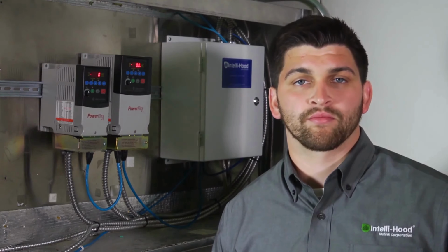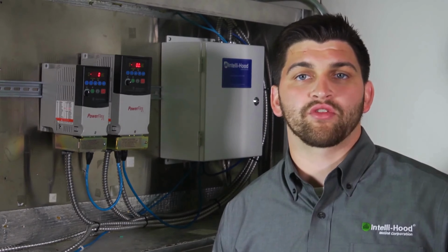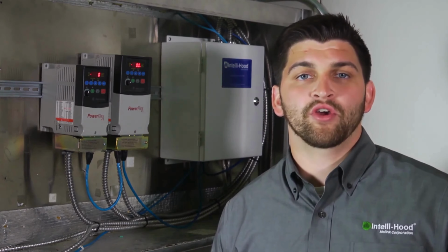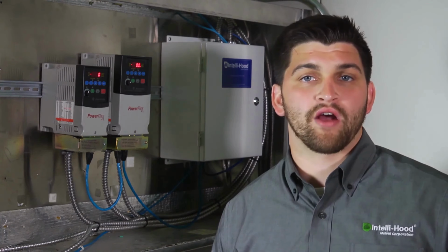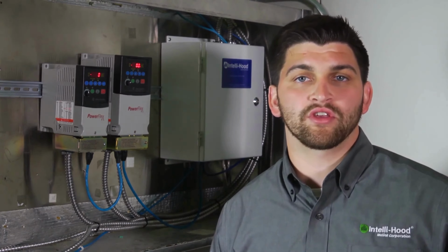For undervoltage faults, check for voltage on all three phases to make sure that all three legs are steady and at the appropriate voltage. This may be caused due to a temporary voltage drop from dirty power or loose connections. For earth faults, check for ground connections. Check the motor for insulation leaks and proper grounding.